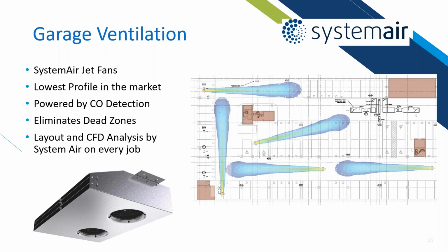So moving on, other residential products that we have available from System Air, we have garage ventilation jet fans. So these jet fans are really amazing. They're only 6 inches deep, and basically they replace all of your ductwork throughout your garage. So using ductwork in a garage to ventilate the space is actually pretty antiquated. What you end up with is a lot of dead zones where CO and NO2 can build up. And what this does is it actually pushes the air from the intake to the exhaust. And if you don't believe me, we have CFD analysis available to prove that.